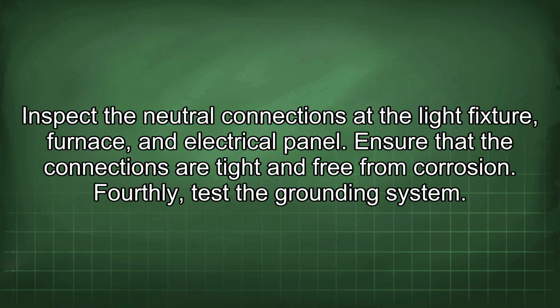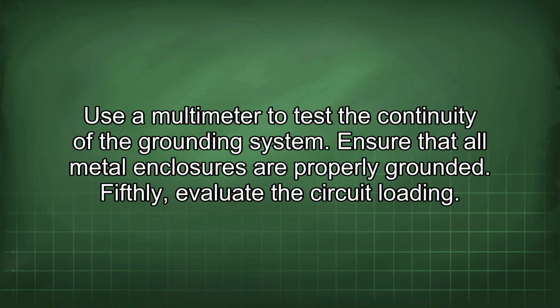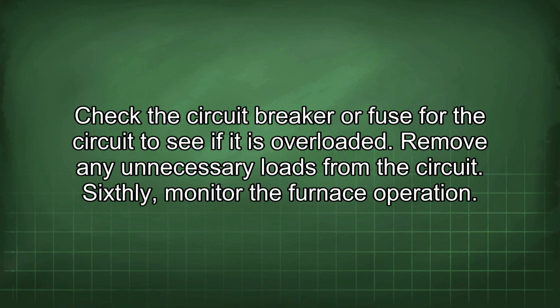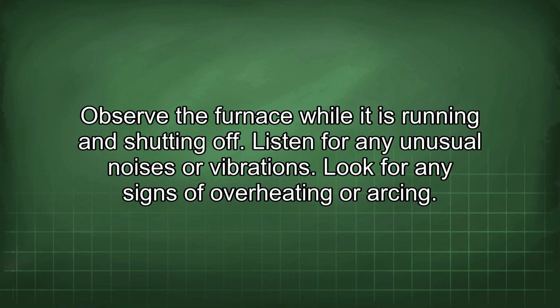Fourthly, test the grounding system. Use a multimeter to test the continuity of the grounding system. Ensure that all metal enclosures are properly grounded. Fifthly, evaluate the circuit loading. Check the circuit breaker or fuse for the circuit to see if it is overloaded. Remove any unnecessary loads from the circuit. Sixthly, monitor the furnace operation. Observe the furnace while it is running and shutting off. Listen for any unusual noises or vibrations. Look for any signs of overheating or arcing.